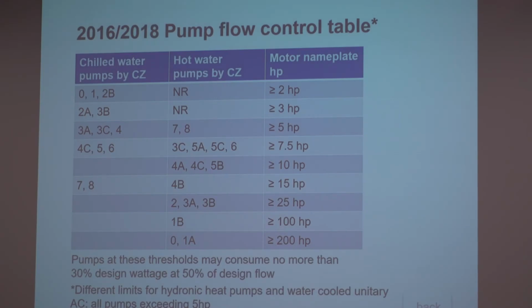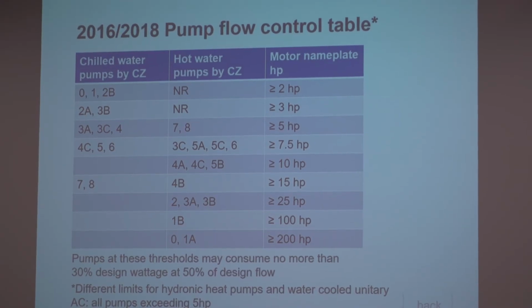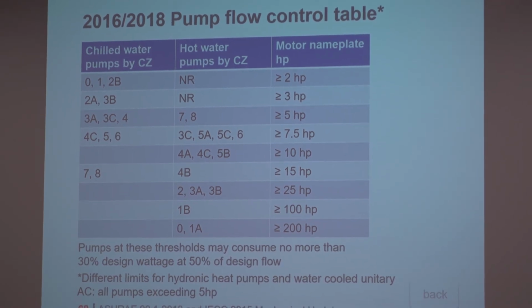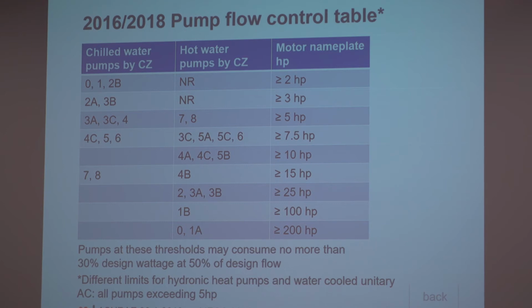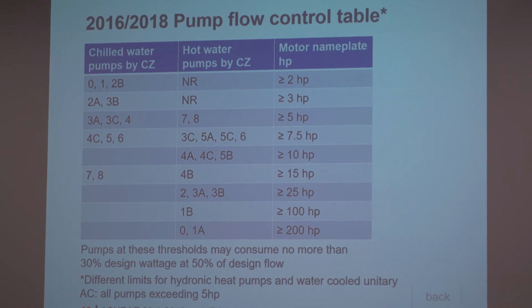The next thing I want to talk about a little bit is pump control. In the past, like I sort of mentioned, we had this 10 horsepower, 5 horsepower sort of VFD requirement. There was a movement underway by some of the really progressive energy conservation wings, if you want to call them, or factions, that wanted to reduce them from 5 horsepower to like 2 horsepower. And we were sort of like, time out. Let's go back and analyze this. And so what happened on the analysis is we found that our existing requirement of 5 horsepower maybe didn't pay back as much as it needed to. And so some of these actually relaxed and some of them went more stringent.